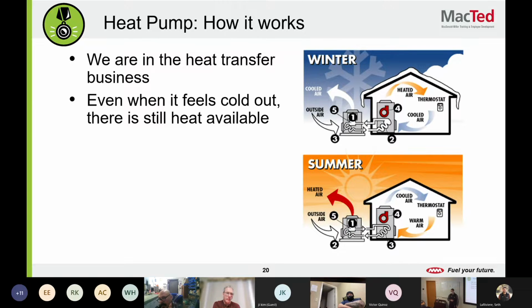I haven't done heat pumps as much with Cater, but I did a lot of heat pumps with my HVAC company. Okay, yeah. So a lot of the issues are maybe the changeover set point wasn't set up. I'd run into this in residential. If I was installing a heat pump with electric heat, you'd have to find that point where, okay, when is the heat pump not keeping up, and when should I just turn on the electric heat, switch over or turn it on to supplement? So there are some different controls and things you need to take into account with that.